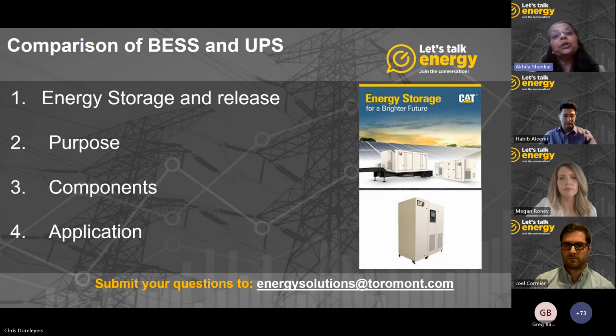In talking about the purpose, a UPS is to ensure the critical devices and systems remain operational without interruption during a power system outage. This allows time either for a safe shutdown of the equipment or for switching over to an alternative power source. The battery energy storage system, on the other hand, plays a critical role in managing the complexities associated with integrating renewable energy sources or maintaining grid stability. And this is, of course, in addition to providing backup power during a power outage.